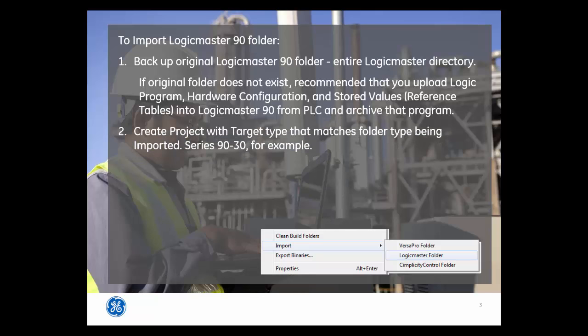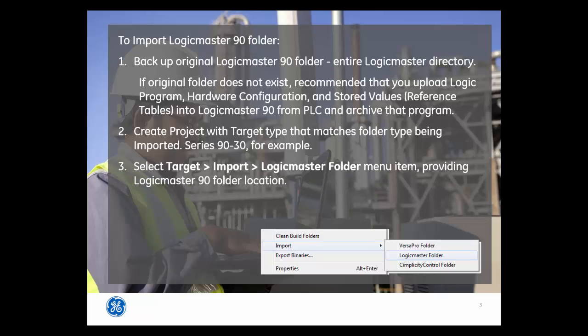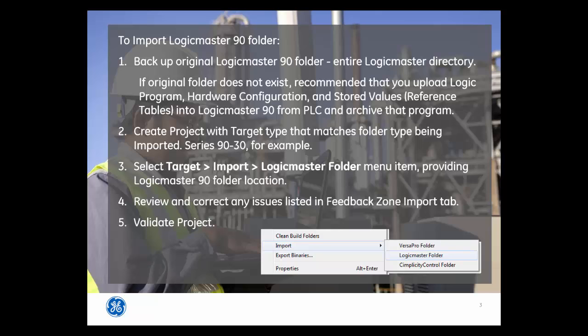Second, create a project with the target type that matches the folder type being imported — Series 90-30, for example. Select the Target Import Logicmaster Folder menu item, providing the Logicmaster 90 folder location. Review and correct any issues listed in the Feedback Zone Import tab. Validate the Machine Edition project.